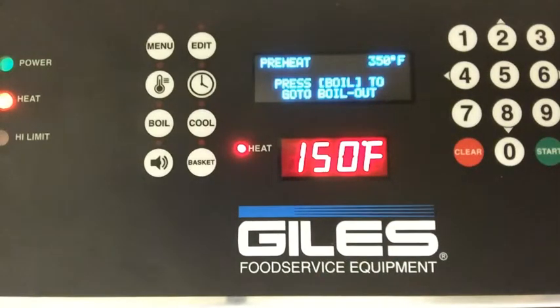Now the reason that we wanted to use that press to start, where it comes up and it gives us the power failure, is the result of our having the ILS turned on, interlocking start, and we'll get into that in a little while when we start setting up and making sure everything is set up for a particular customer. But the ILS being on will give you that message. If you turn that off, it'll skip that and go straight into the preheat mode.